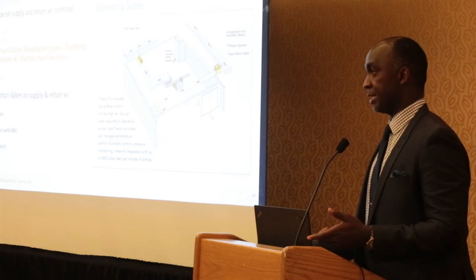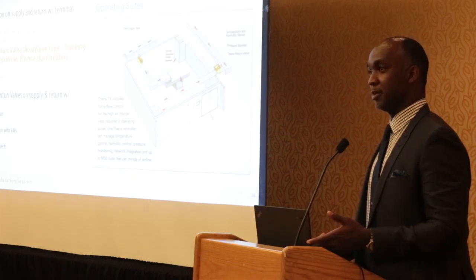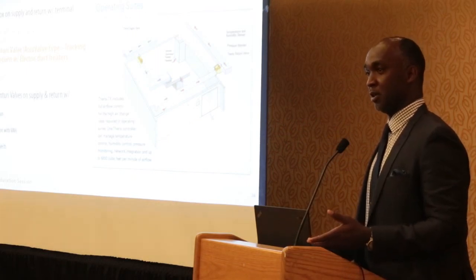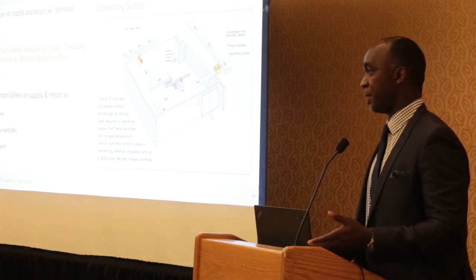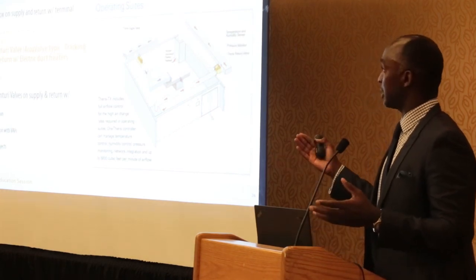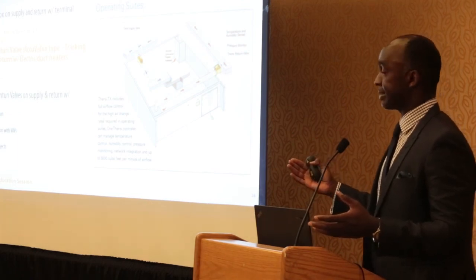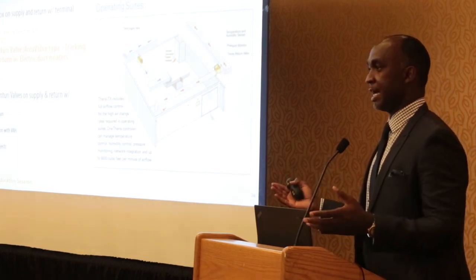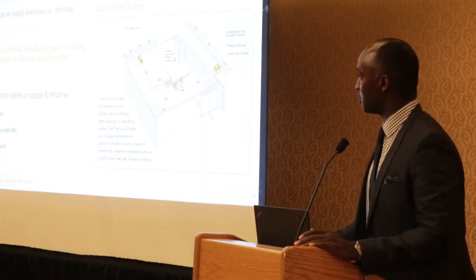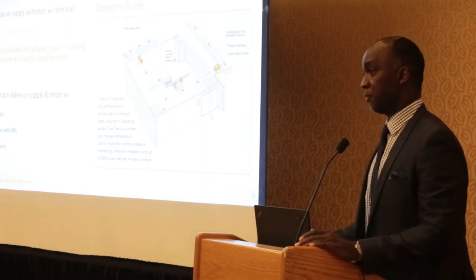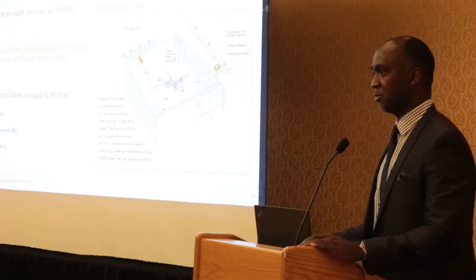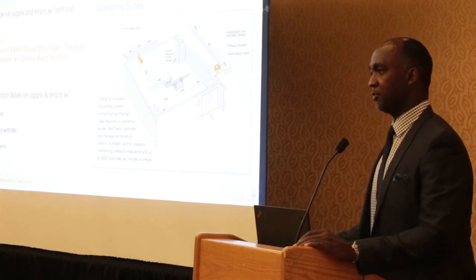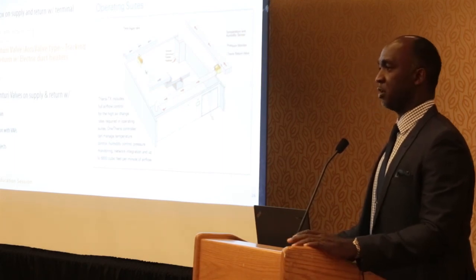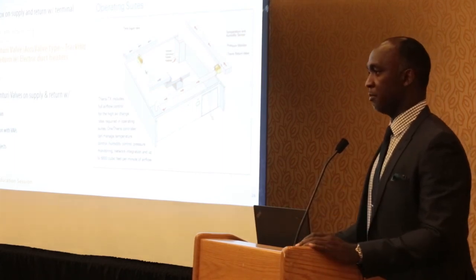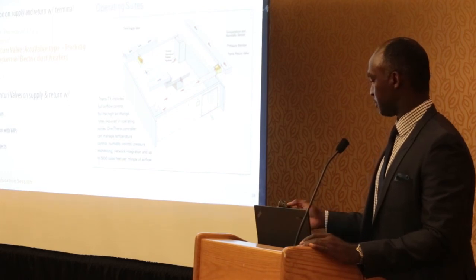We're talking about people's lives, so I don't think we should be debating on the best means of actually maintaining pressure in that space. Venturi valves are extremely accurate. They're slightly more expensive than a VAV, but that's what we recommend for a hybrid OR space. There's an extension, the Phoenix valve, which is almost the same but a little more expensive. If you're doing a renovation project, a Phoenix valve is much more expensive, and it's difficult to mix and match Phoenix valves with a VAV system.